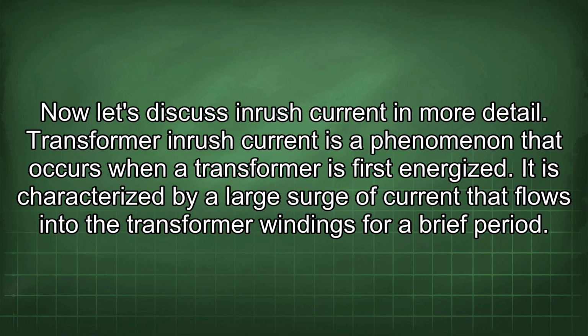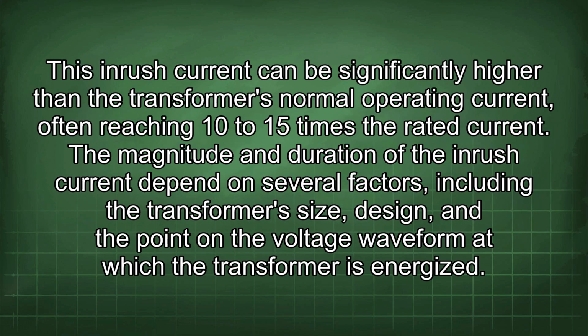Now let's discuss inrush current in more detail. Transformer inrush current is a phenomenon that occurs when a transformer is first energized. It is characterized by a large surge of current that flows into the transformer windings for a brief period. This inrush current can be significantly higher than the transformer's normal operating current, often reaching 10 to 15 times the rated current. The magnitude and duration of the inrush current depend on several factors, including the transformer size, design, and the point in the voltage waveform at which the transformer is energized.